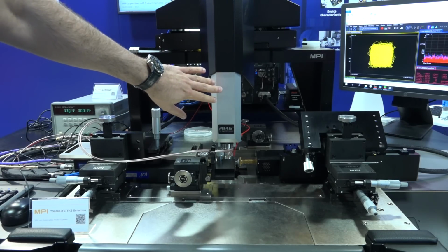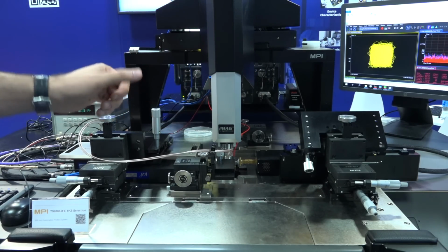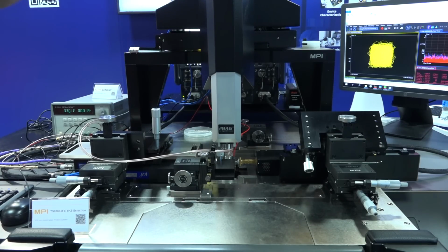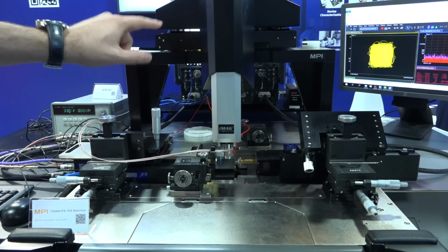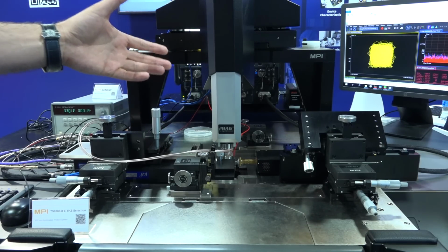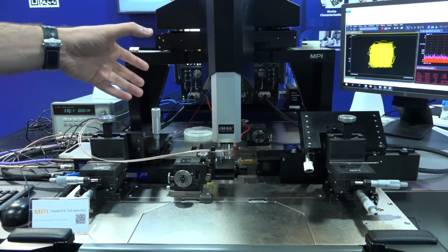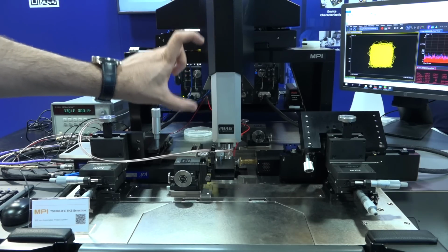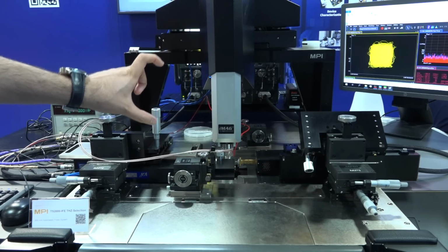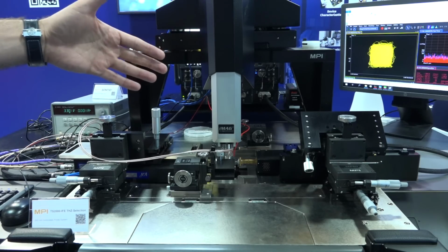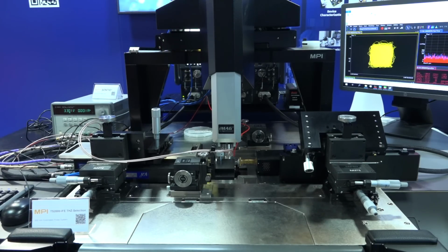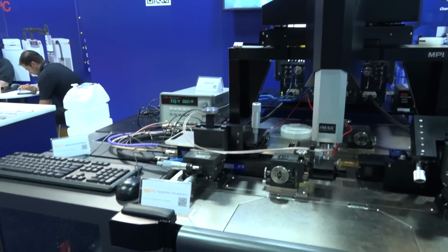We do have a full digital camera in the front with a large working distance. A large working distance on these microscopes is pretty important because in a waveguide setup, you have the rigid waveguides coming out of the probe. And because there are so many circuit configurations and you don't know where your probes are going to be, you want to make sure you have enough clearance to actually see what you're doing. And especially with a fully digital camera like this, and things can be moving around, you want to make sure nothing crashes.